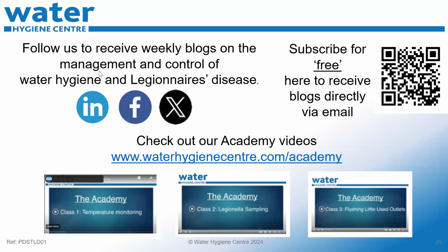Excellent. Russell asks, in schools, we ensure delivery at around about 43, not 50, aware of storage above 60, with return on cover for above 50, but do cooler than 50 delivery matter? So, it sounds to me as though you may well have TMVs. So you may mix the water to that 43 degrees C, and your flow to that TMV would probably be greater than 50. Worth checking, but most schools have got a lower appetite for risk from a scalding perspective.